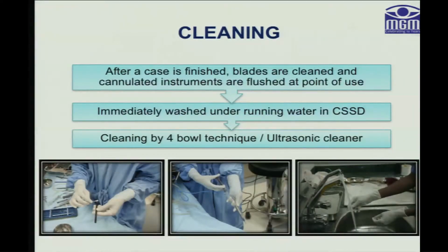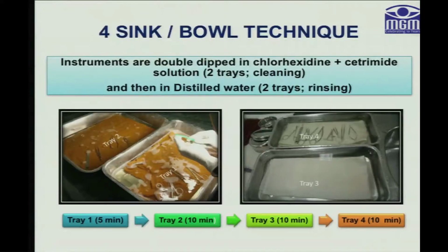Next step is the cleaning. After a case is finished, the blades are cleaned and cannulated instruments are flushed at the point of use, then immediately washed under running water. And then cleaning is done by the 4-bowl technique or using an ultrasonic cleaner. In the 4-bowl technique, the instruments are double dipped in chlorhexidine cetrimide solution in the 2 trays where the cleaning is done, and then rinsing is done in another 2 trays filled with distilled water.